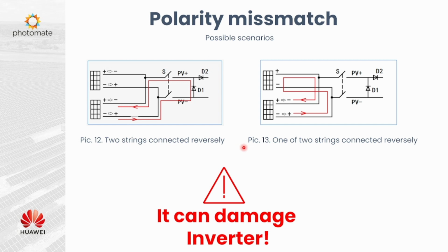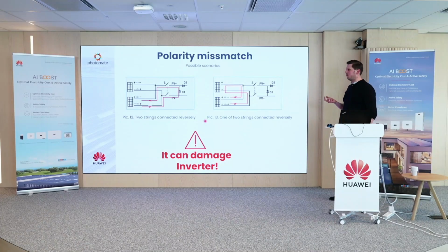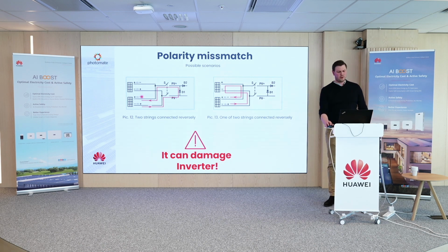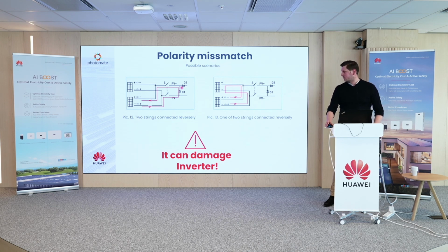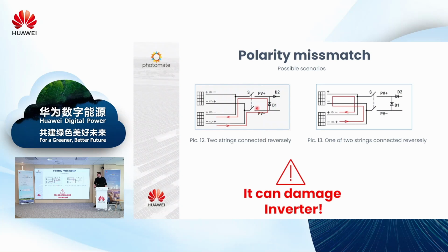First, let's say two most typical scenarios of how it happens and what happens. The first case is not so dangerous, because when you have the polarity mismatch of two strings connected to one MPP tracker, the short circuit path through the PV modules will look like this, of course. So this diode will not block this current anymore, but it will allow it to flow. And it is like the pure short circuit current of your PV generator. So if you try to disconnect the DC switch during this operation or remove the connectors, you might damage it.